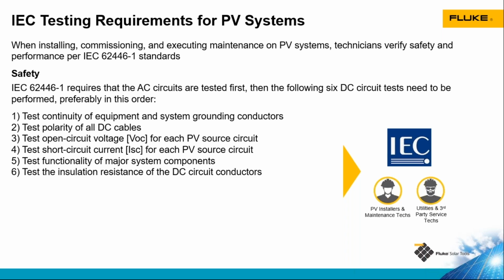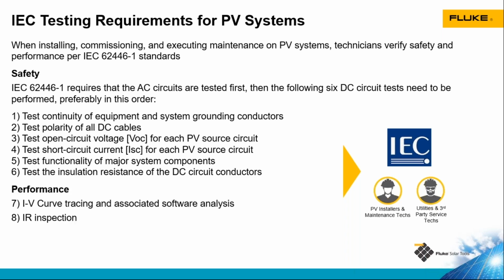We're also going to check the polarity, open circuit voltage, and short circuit current of our DC circuits. We'll check to make sure that all of our major components are functioning properly, so our disconnects work, our inverter is converting DC to AC at the appropriate efficiency. And then finally, we're going to test the insulation resistance of our DC conductors to make sure that the conductors weren't damaged during installation or operations and maintenance. Once we've done the safety tests, the category 1 tests, we're going to do the category 2 tests. These are optional tests for performance, and these include IV curve tracing to make sure our modules and strings of modules are working properly, and thermal imaging to make sure there are no hot spots or cool spots to see if there's no current flowing through a circuit.